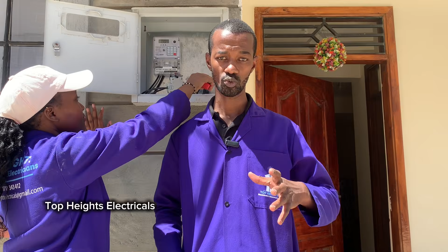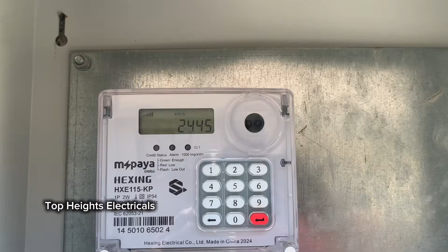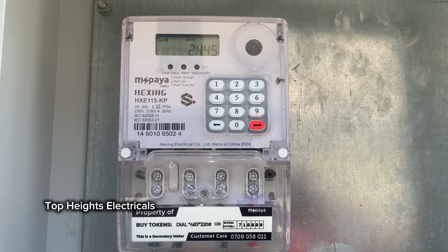My top boss, today we are at our customers' residence and we are here to check the issue with safety. There is a problem with earthing. We have confirmed that the meter box is not properly wired and also the earth rod is missing. Customer is not protected. So that is what we are here for. Even to begin with, you notice that there is a lot of mistakes on this meter box.